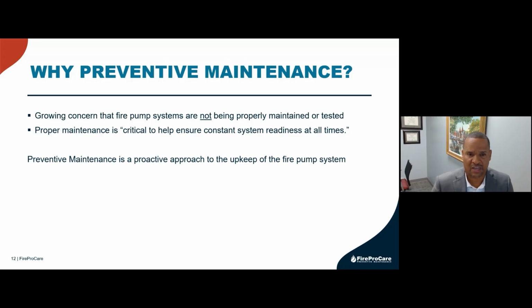The customer now has no reason to not test the system if it can be done remotely, because today it requires someone to be on site, and time and manpower is always an issue. Can you get by there to take care of it and make sure it's been maintained properly? It depends. The annual tests, like I said earlier, are always handled. But what if the manufacturer says it should be maintained on a weekly basis? Do you have the manpower to do that? Sometimes you don't, and when they don't, they skirt around the system and maybe not test it. Someone may sign off on it. That's part of the problem. How do we know it really did happen? We don't.